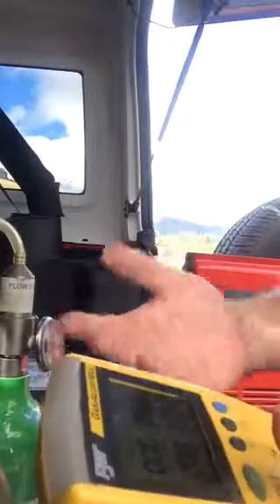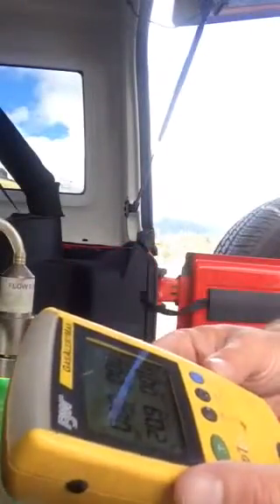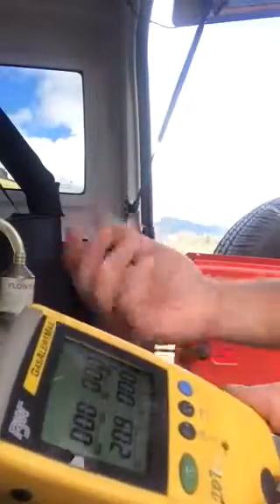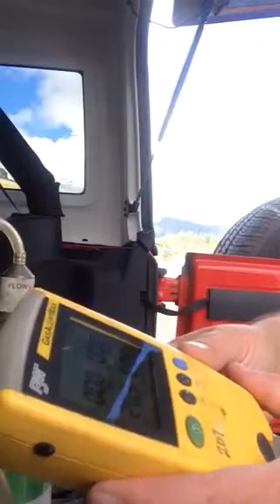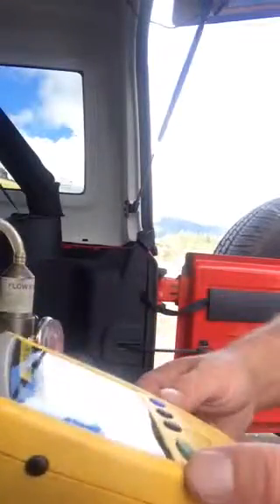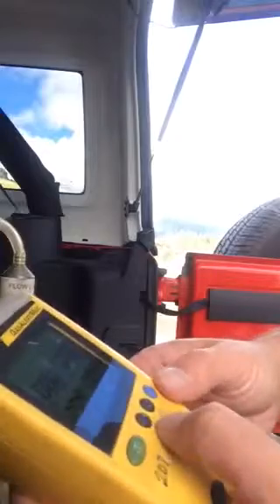It's also a good idea to keep the batteries charged, and occasionally, I know you guys don't use these very often here in Hawaii, but it's a good idea to start them up, hit them with the bump gas. The sensors in these tend to go dormant, and when it comes time to use them, even if they're within calibration, they won't work properly. The sensors will just go bad. Alright, so this thing's ready to go.